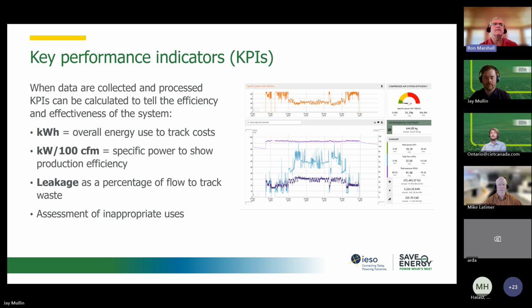compressors, right? And then if a study is done or observations made, even internally, you can make a list of potentially inappropriate uses like blowing for cleaning, like using air motors instead of electric, things like that, that could be either eliminated, optimized, or maybe looked at in a different manner, do some engineering on it, and pick away at those to get rid of the compressed air load as well.